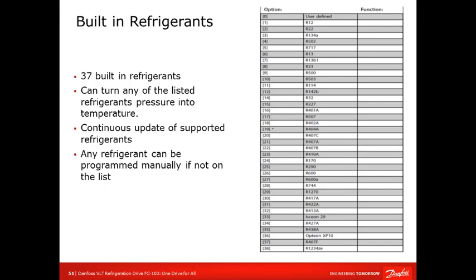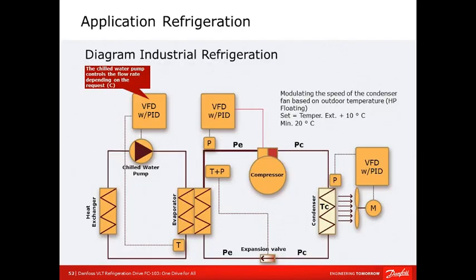One of the things with this product is we have a built-in refrigerant table. This is just an example where, if you're using ammonia, it'll take the properties of the refrigerant into account. So Danfoss has integrated the process control into the FC-103, providing flexibility either to the controller or to use the PID functionality, a control loop feedback of the FC-103, so you can follow the set point value, for example temperature. It just makes it easy when they're commissioning the drive. So there are a lot of things we try to include.